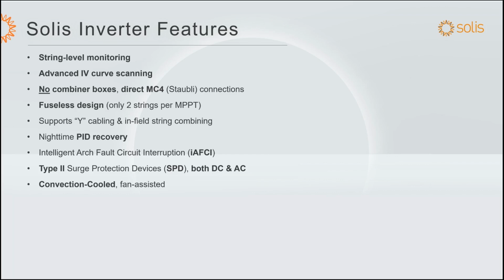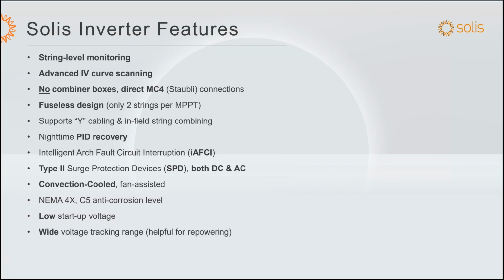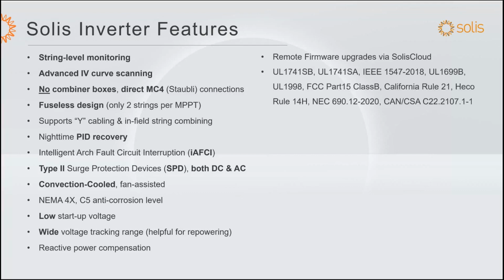Convection cooled, but fan assisted. So the inverters will operate without fans going, but you do have fans for more cooling. NEMA 4X C5 anti-corrosion level for the enclosures. Low startup voltage and very wide MPPT tracking range. So again, you'll see why that's important for repowering. Reactive power compensation, if that's required for your site. We can do remote firmware upgrades via our Solis cloud, and that's our monitoring platform. And next, we meet all of the standards that you could think of, as shown here.